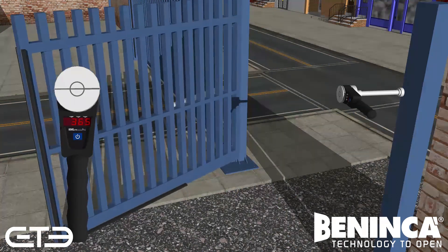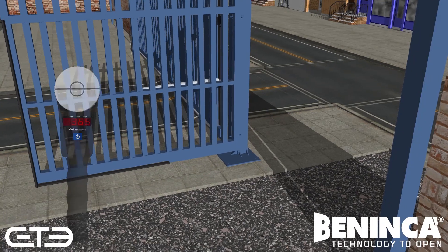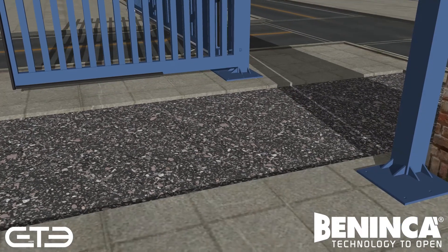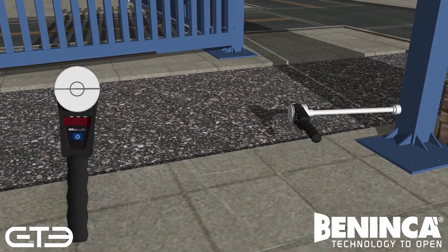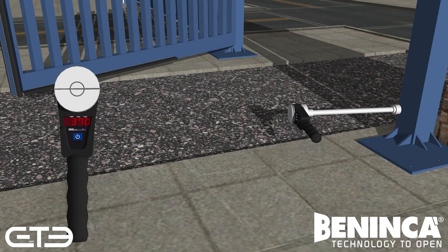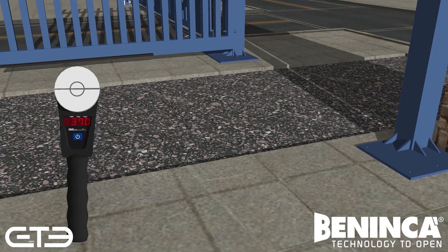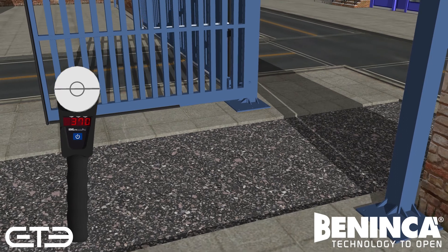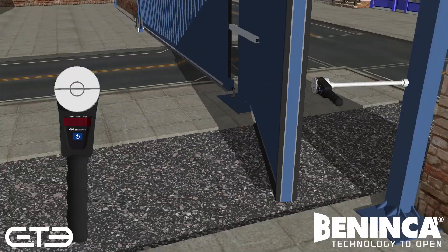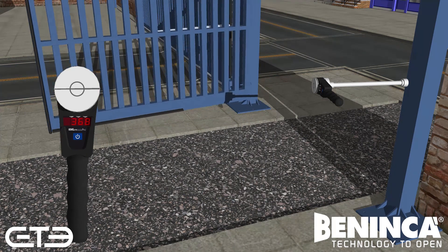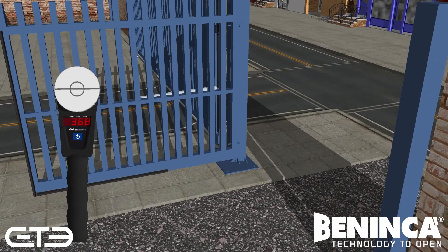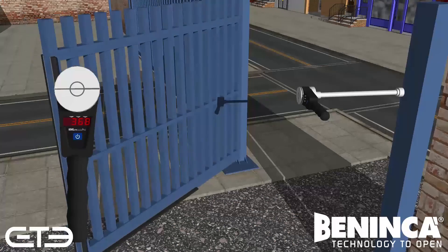For the last test, attach the second extender to the instrument and place the extender against the stop post for your 18th reading. Place it 50mm up and 500mm across. Initiate and test three times to gather your results for the average. Repeat for halfway up, 500mm across, and then 300mm down, 500mm across.